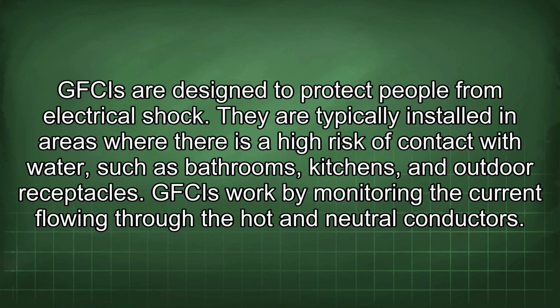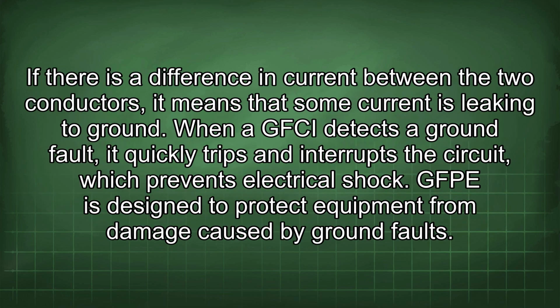GFCIs are designed to protect people from electrical shock. They are typically installed in areas where there is a high risk of contact with water, such as bathrooms, kitchens, and outdoor receptacles. GFCIs work by monitoring the current flowing through the hot and neutral conductors. If there is a difference in current between the two conductors, it means that some current is leaking to ground. When a GFCI detects a ground fault, it quickly trips and interrupts the circuit, which prevents electrical shock.